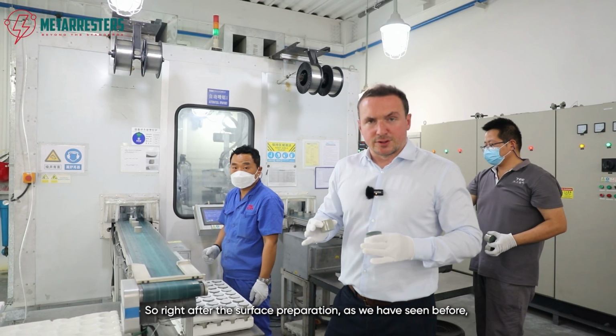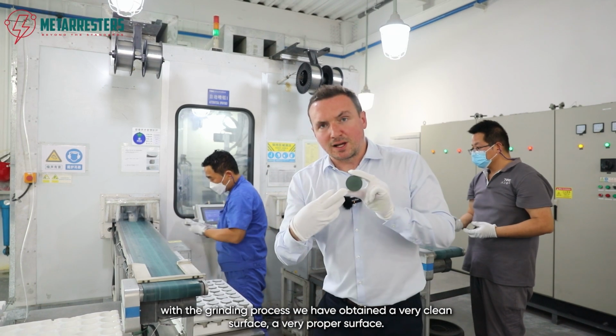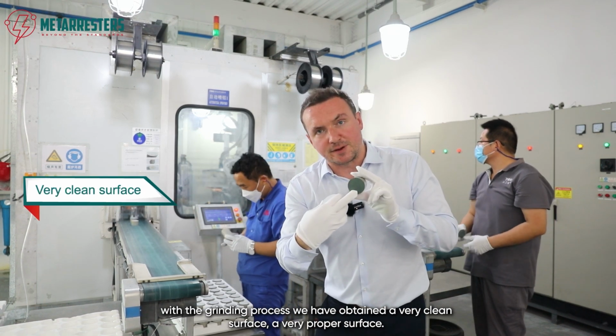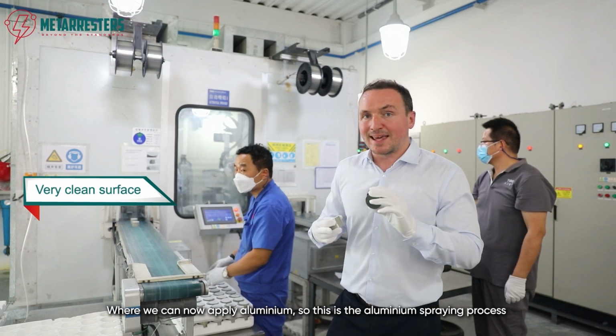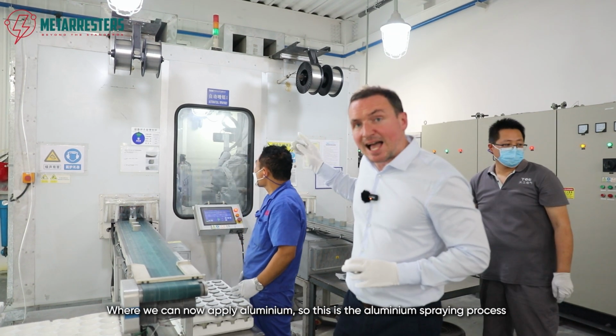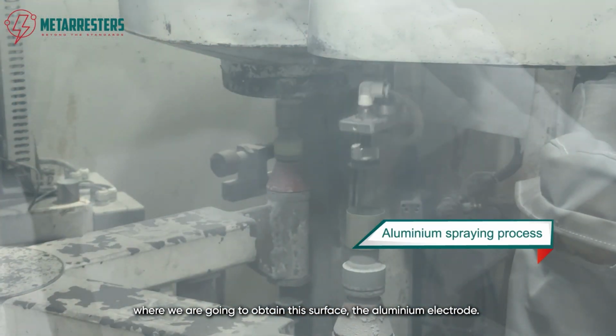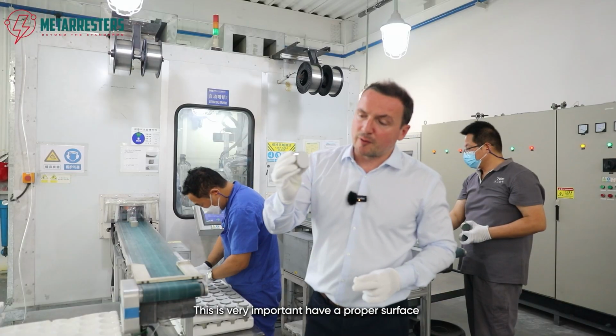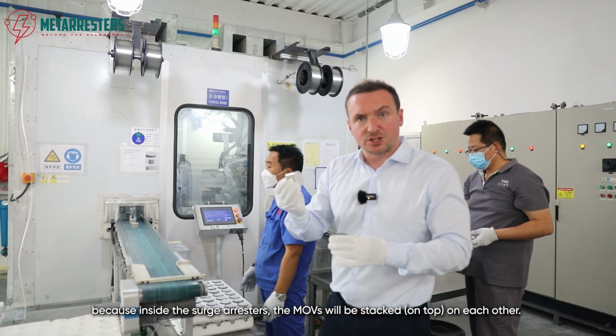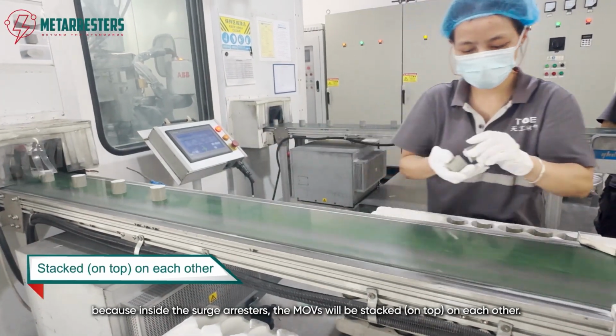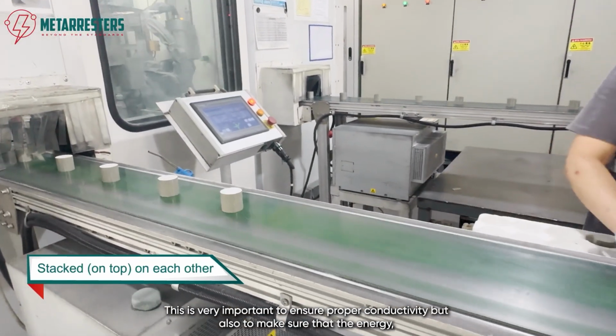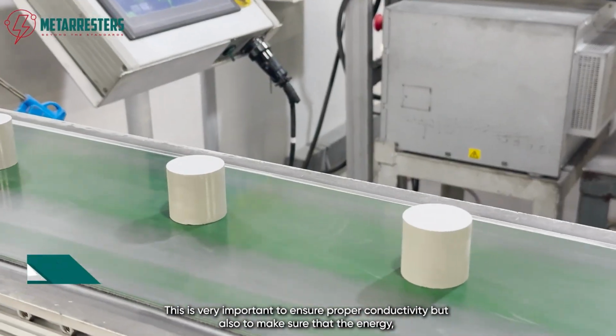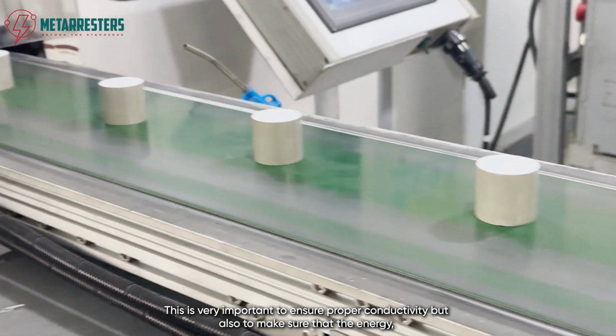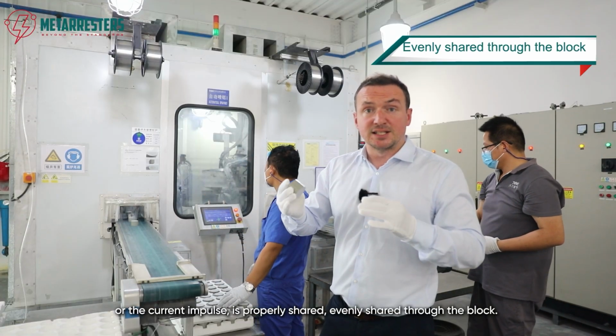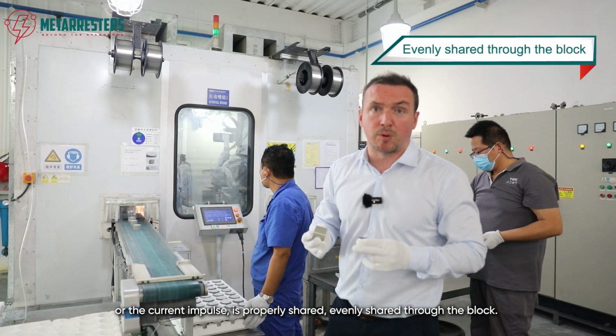So right after the surface preparation, as we have seen before, with the grinding process, we have obtained a very clean surface, a very proper surface, and we can now apply aluminium. So this is the aluminium spraying process, where we are going to obtain this surface, the aluminium electrodes. This is very important to have a proper surface, because inside the arresters, the MOV blocks will be stacked on each other. This is very important to ensure proper conductivity, but also to make sure that the energy or the current impulse is properly and evenly shared through the block.